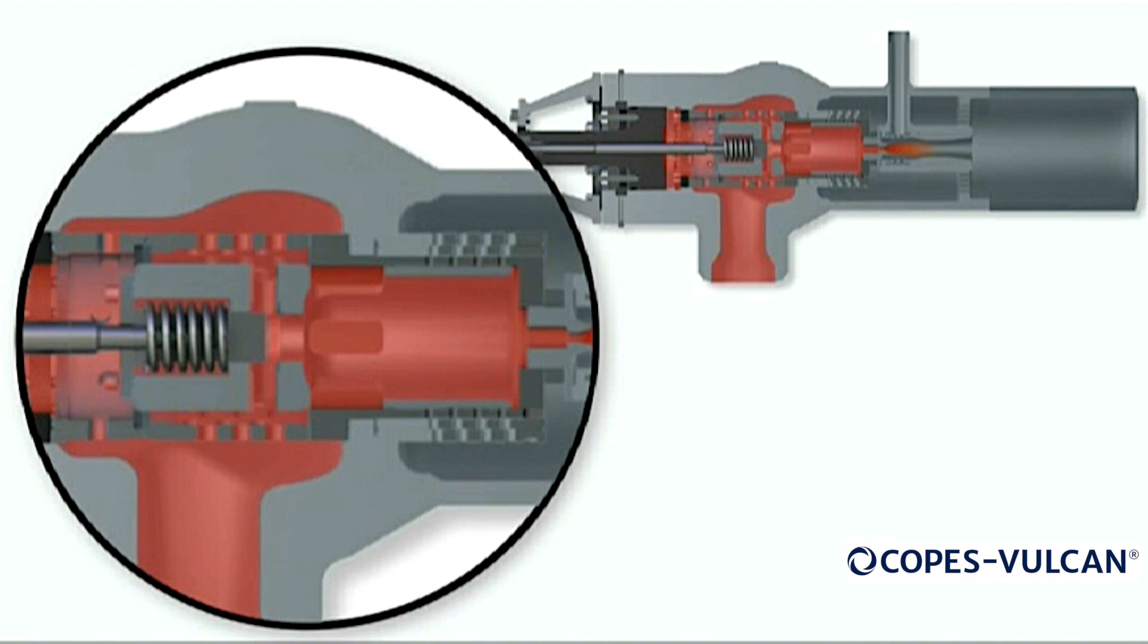Some other designs employ low pressure, or P2 balancing. However, these low pressure balancing systems rely on auxiliary balancing seals, such as piston rings and close tolerance sealing surfaces, to prevent the high pressure steam unbalancing the trim. In operation, if these seals or surfaces wear or become damaged, the trim quickly becomes unbalanced, and stem loads dramatically increase and fluctuate, which can result in the valve oscillating violently or even unable to open on command.